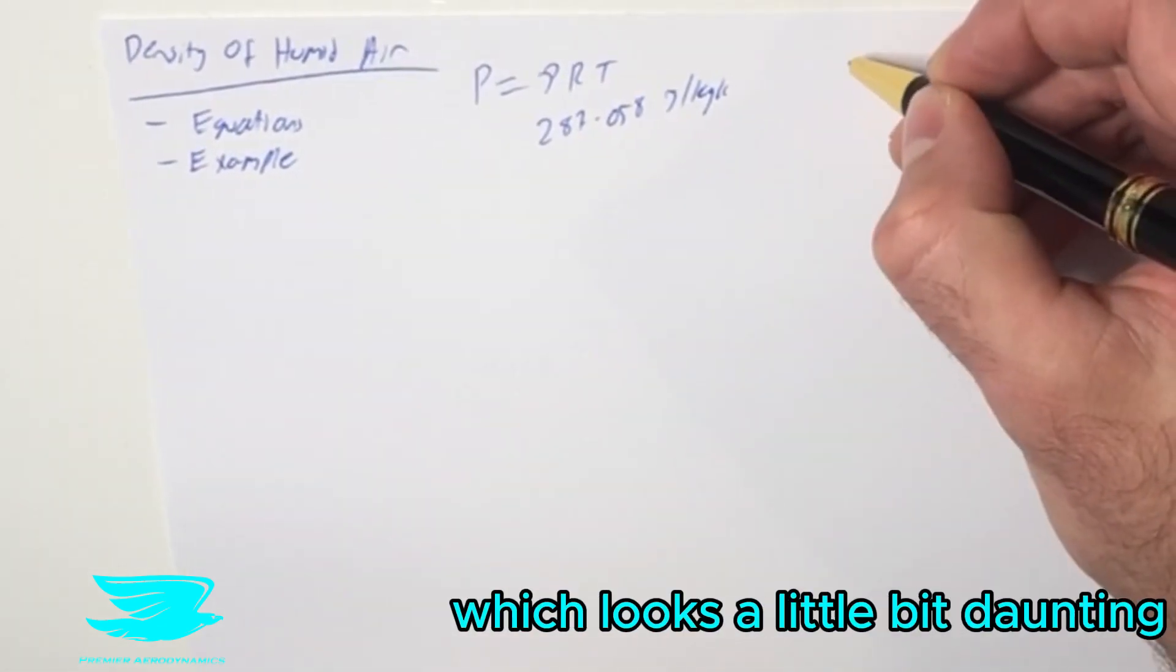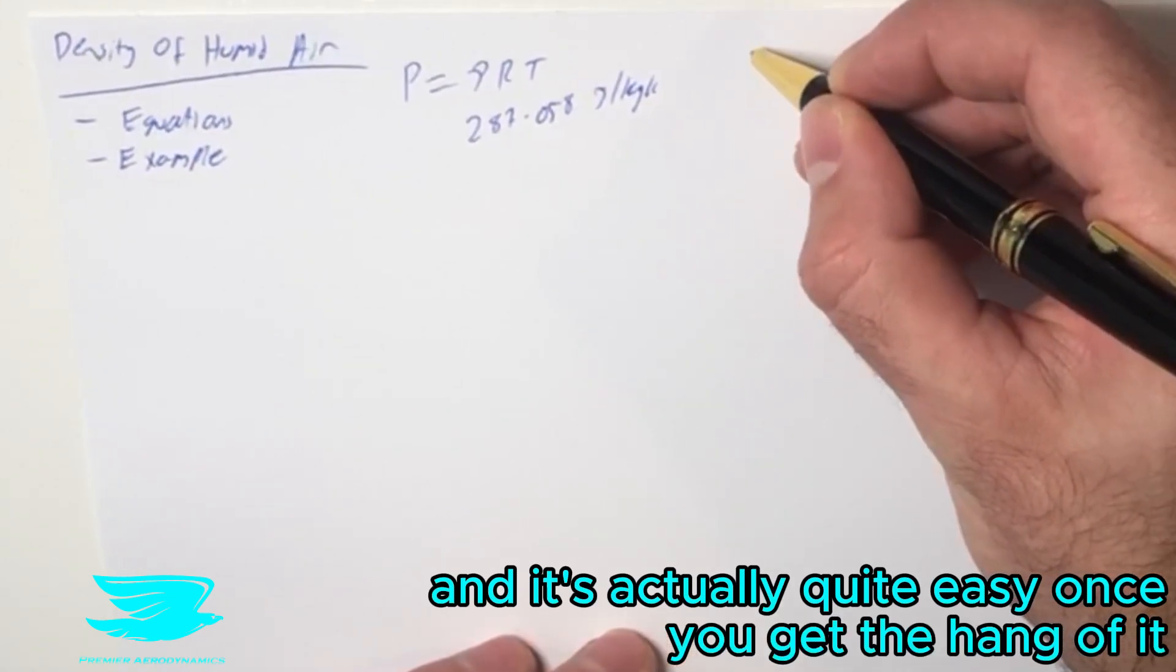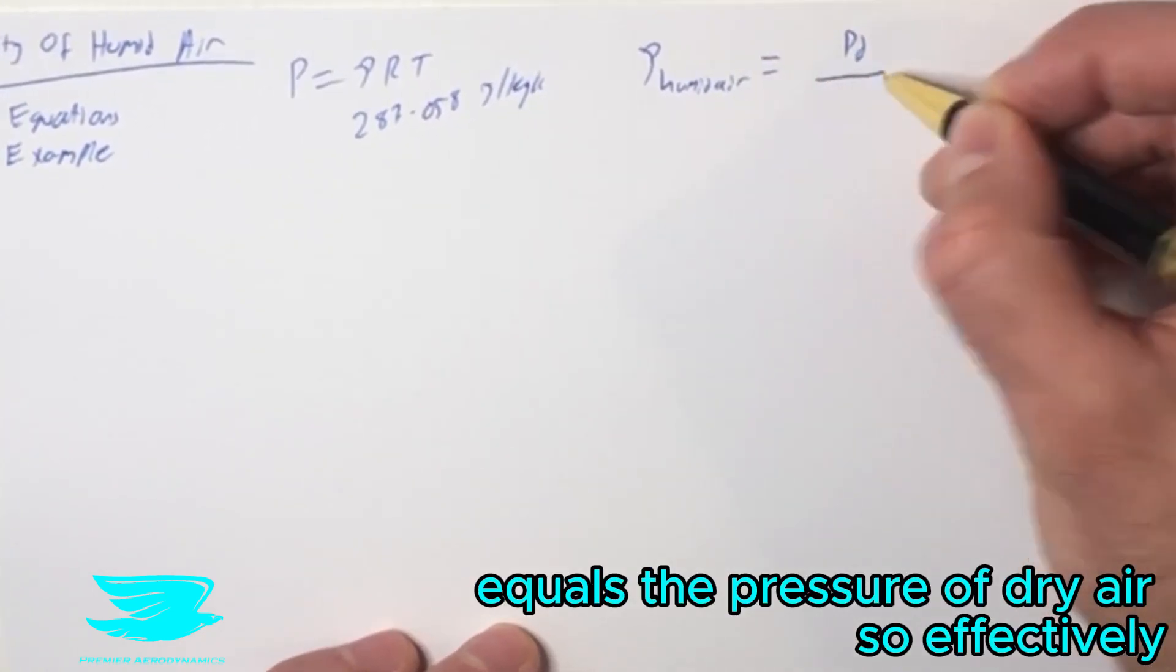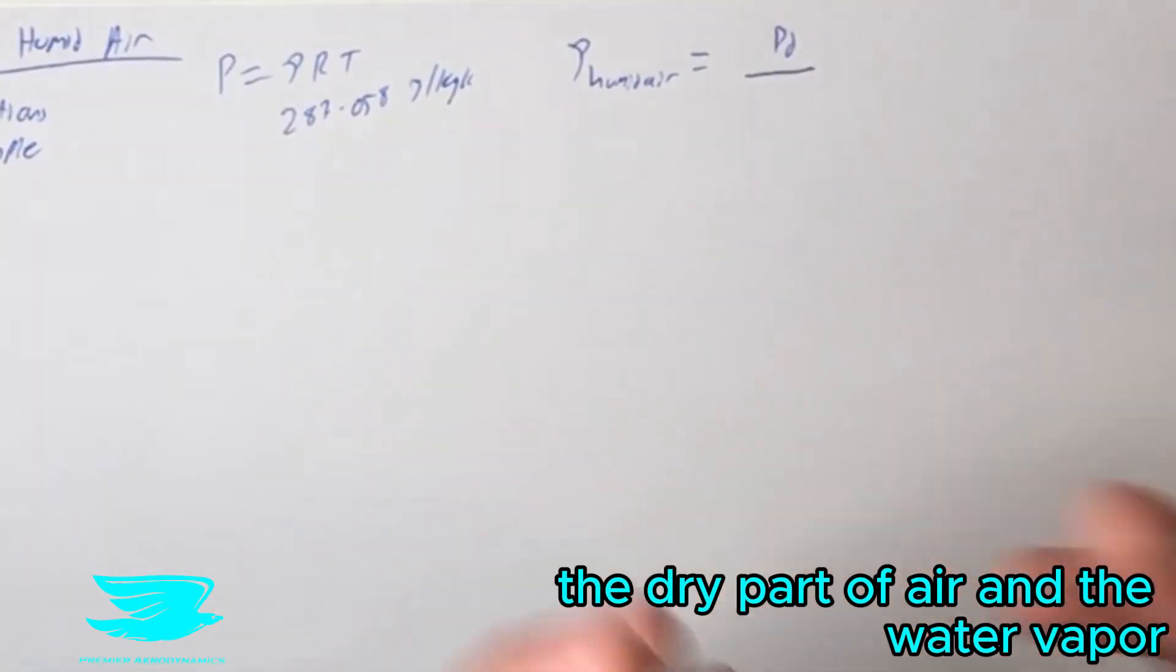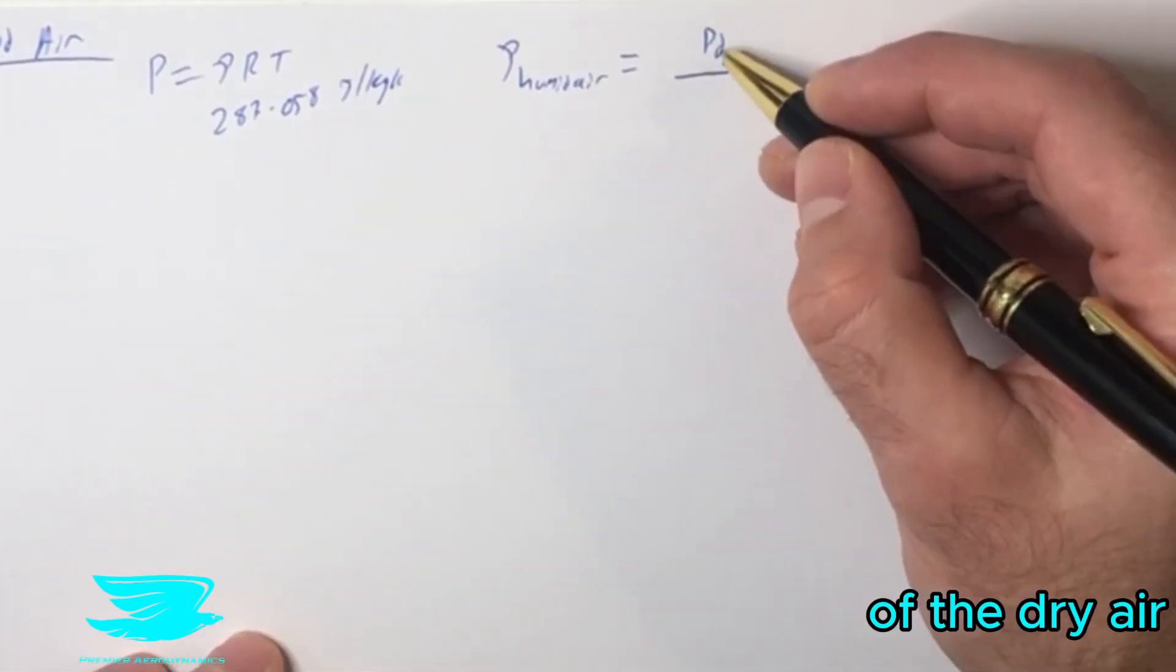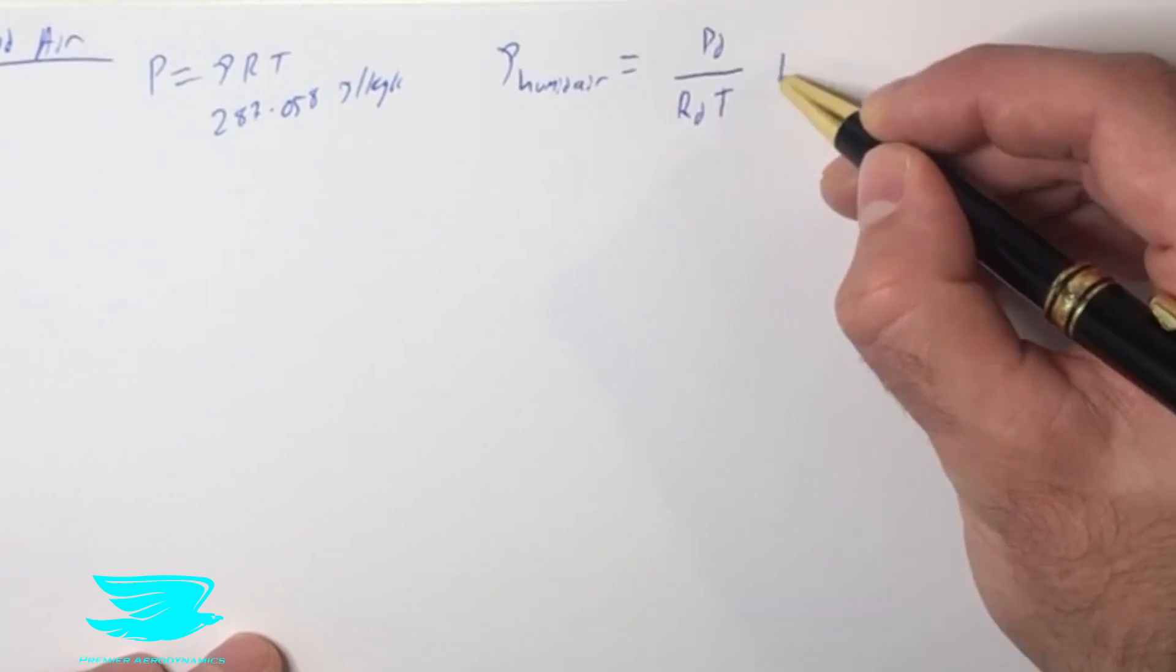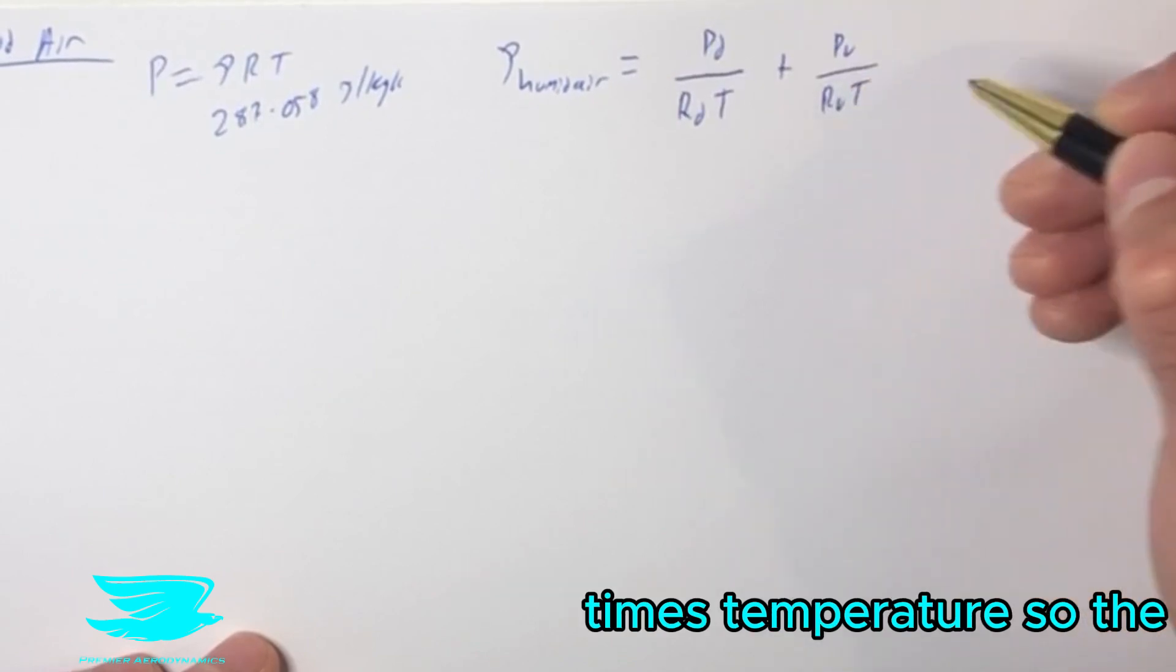We use one equation here, which looks a little bit daunting, but we'll go through it step by step. The density of air equals the pressure of dry air, so we're effectively segregating the pressures that the dry part of the air and the water vapor are creating. The pressure of density of the dry air divided by the gas constant of the dry air times the temperature, plus the pressure of the water vapor divided by the gas constant of the water vapor times temperature.